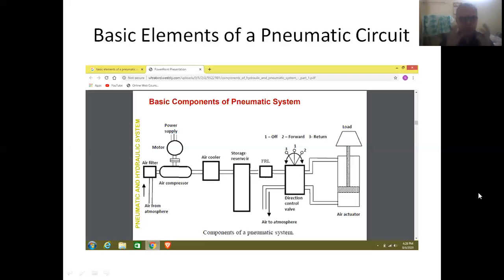So we have to make arrangements for providing lubrication between the piston and the cylinder. Air is a dry fluid, so we have to send air along with a certain quantity of lubricating oil. We have to mix both these fluids, so we use an element called a lubricator.